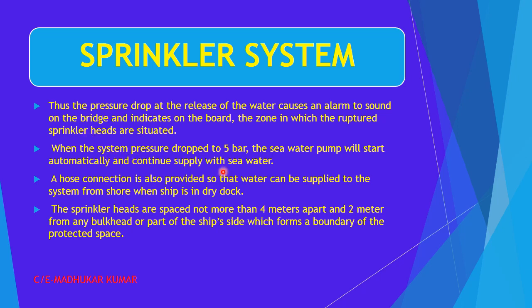When the system pressure drops to 5 bar, meaning the pressure in your tank and the complete system, if the pressure switch senses that it has dropped to 5 bar or less, then the seawater pump automatically gets a signal and starts supplying the seawater. The hose connection is also provided so that water can be supplied to the system from shore, for example if it is not possible to operate these pumps in dry dock. You also have the shore connection facility, which we have seen in the main diagram.